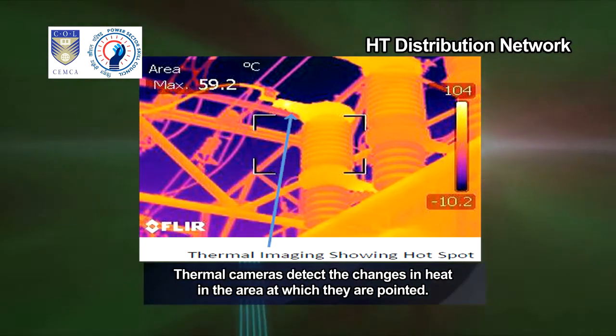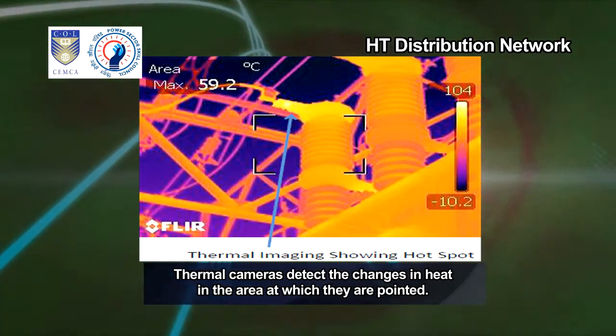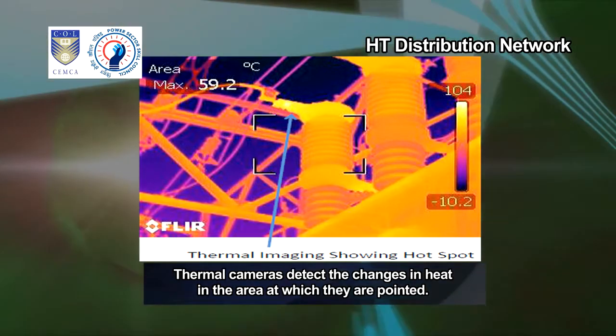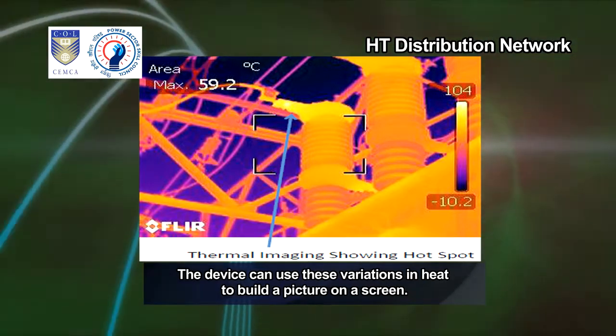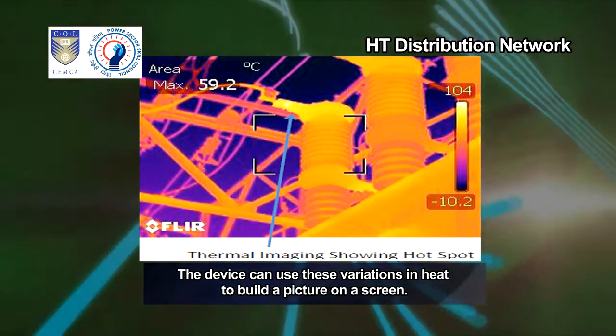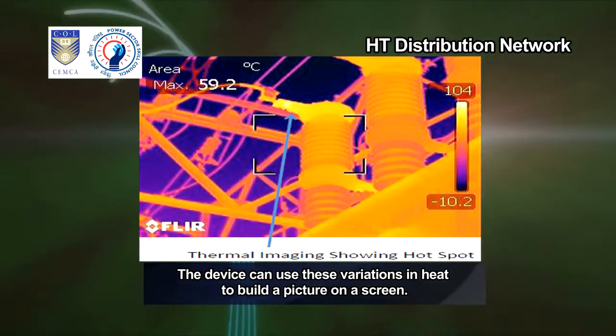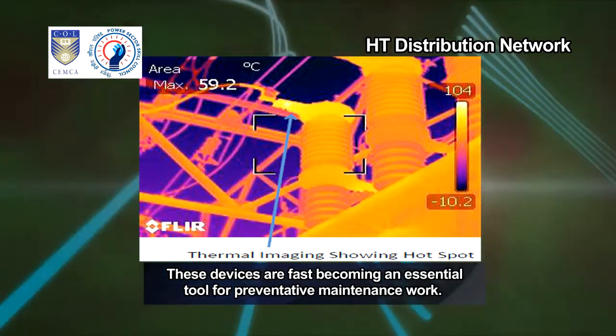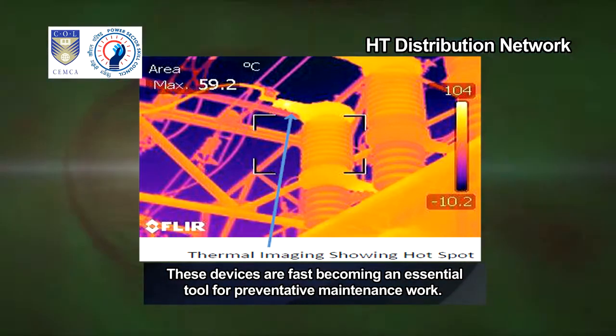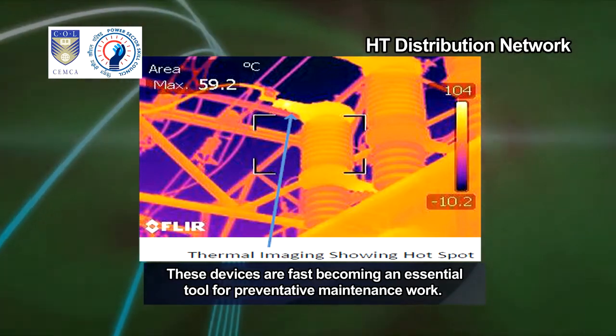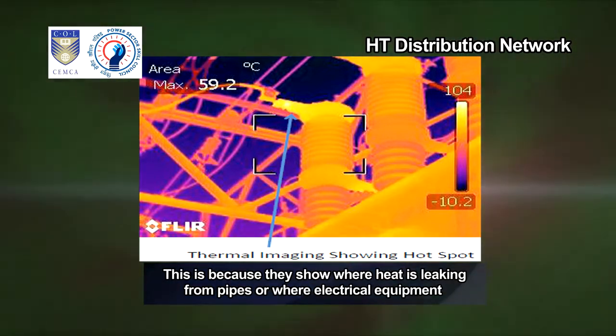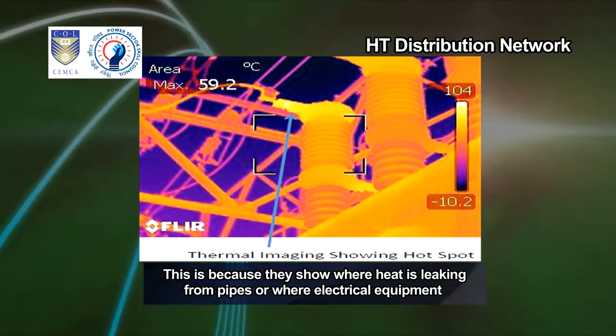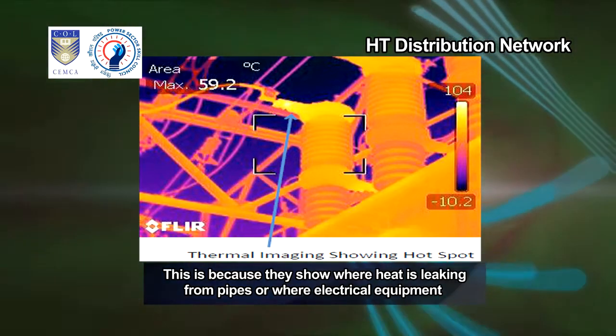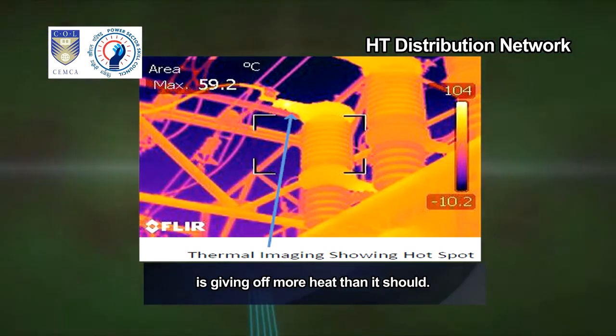Thermal cameras detect the changes in heat in the area at which they are pointed. The device can use these variations in heat to build a picture on a screen. These devices are fast becoming an essential tool for preventative maintenance work.